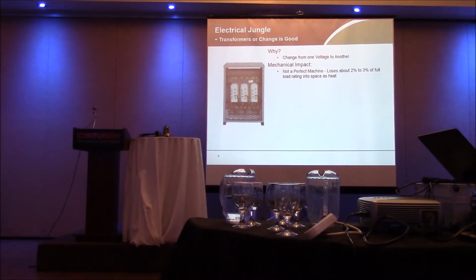So a transformer is not a perfect machine. We've got to ventilate it. And when they're fairly large - say you came to me and said you want to run your big chiller at 208 volts, and it's a 500 horsepower chiller - I have to use a transformer at 1000 kVA, with a heat load of 20 kilowatts when that transformer is operating at full load. So you've got to get 20 kilowatts of heat out of that room.